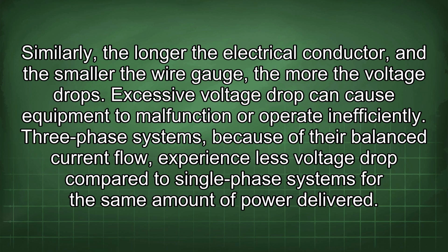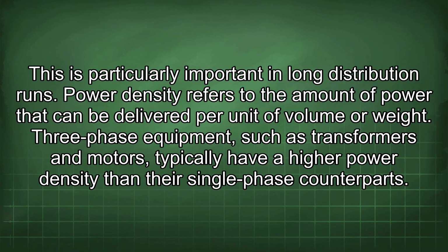Excessive voltage drop can cause equipment to malfunction or operate inefficiently. Three-phase systems, because of their balanced current flow, experience less voltage drop compared to single-phase systems for the same amount of power delivered. This is particularly important in long distribution runs.